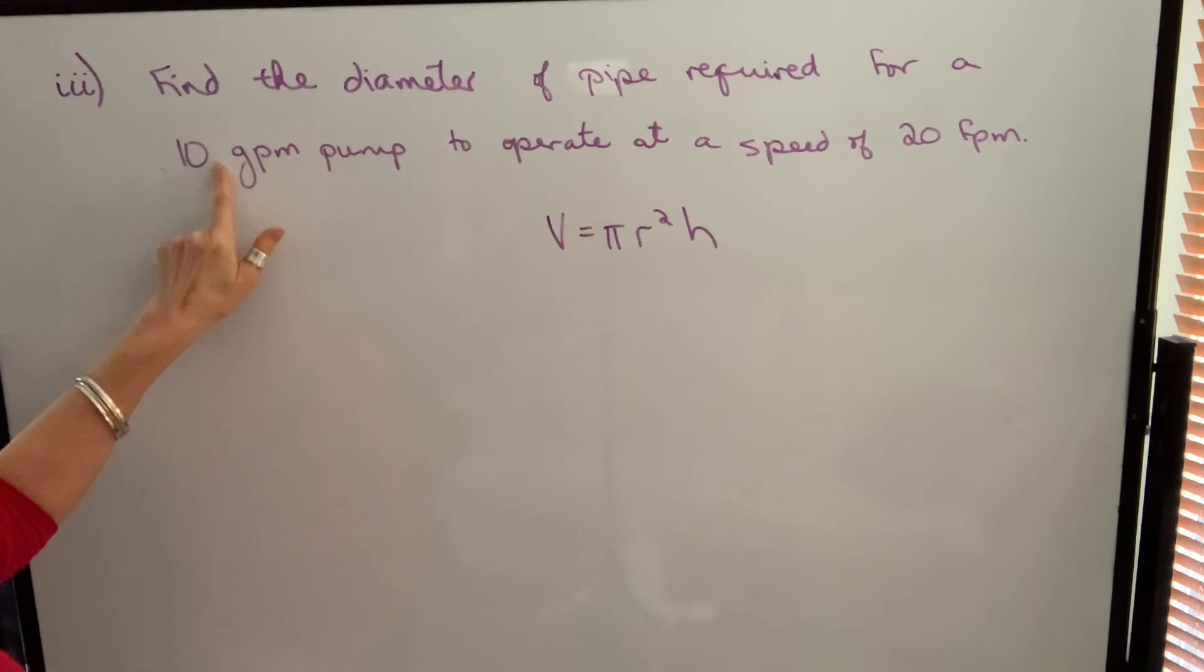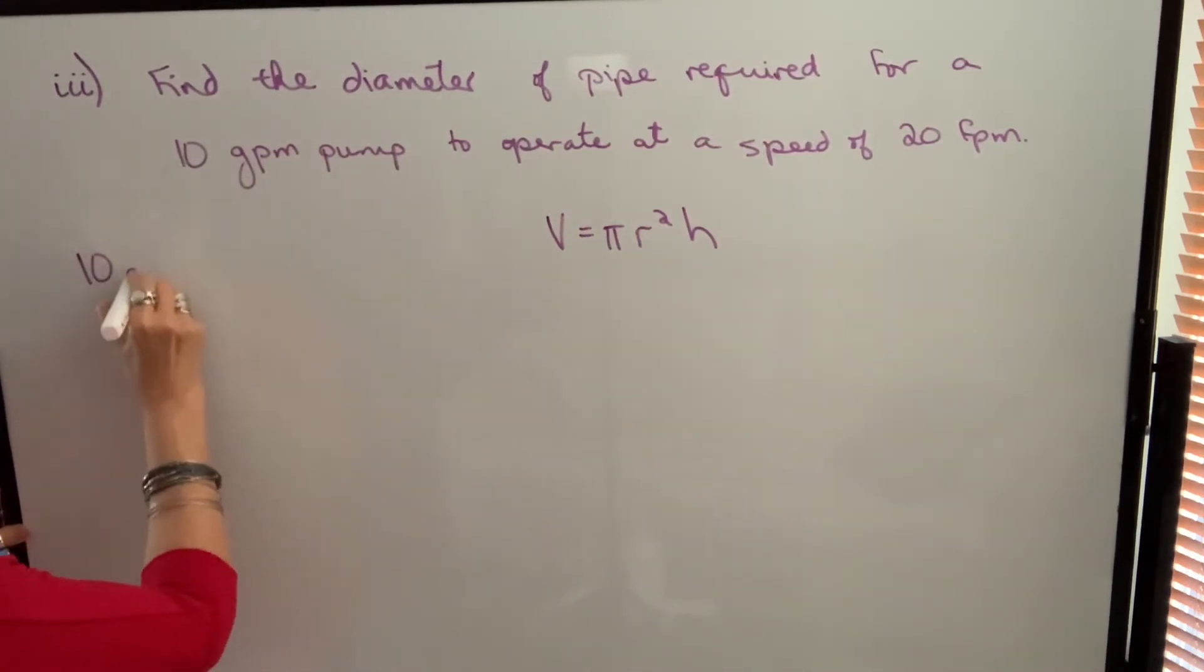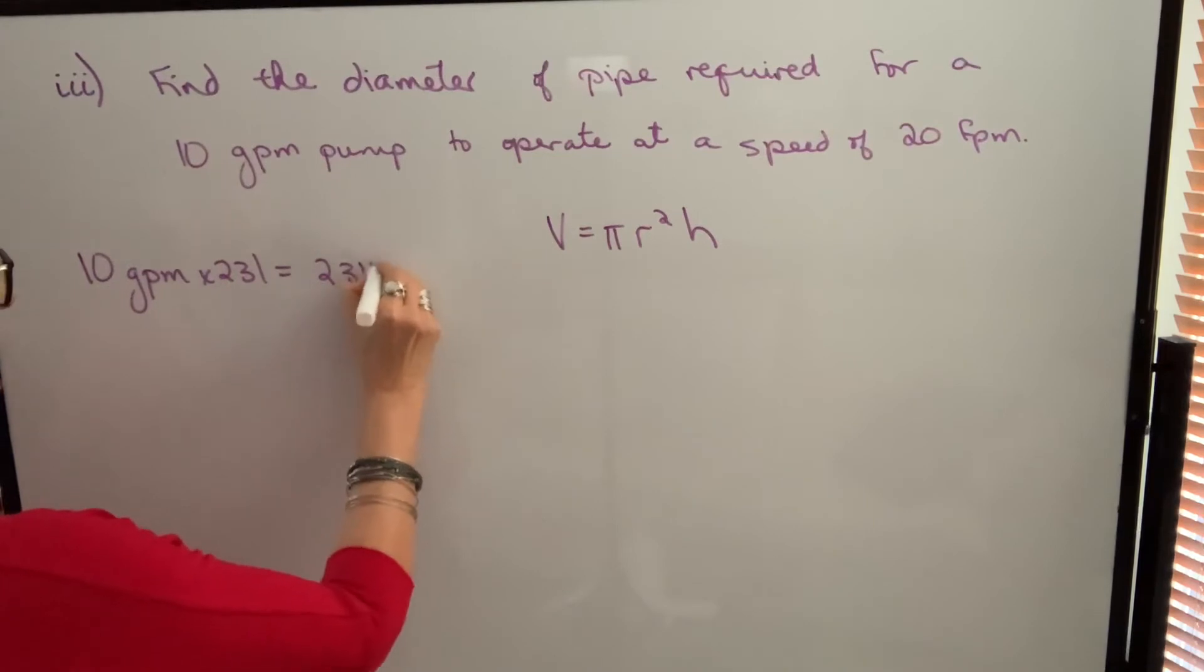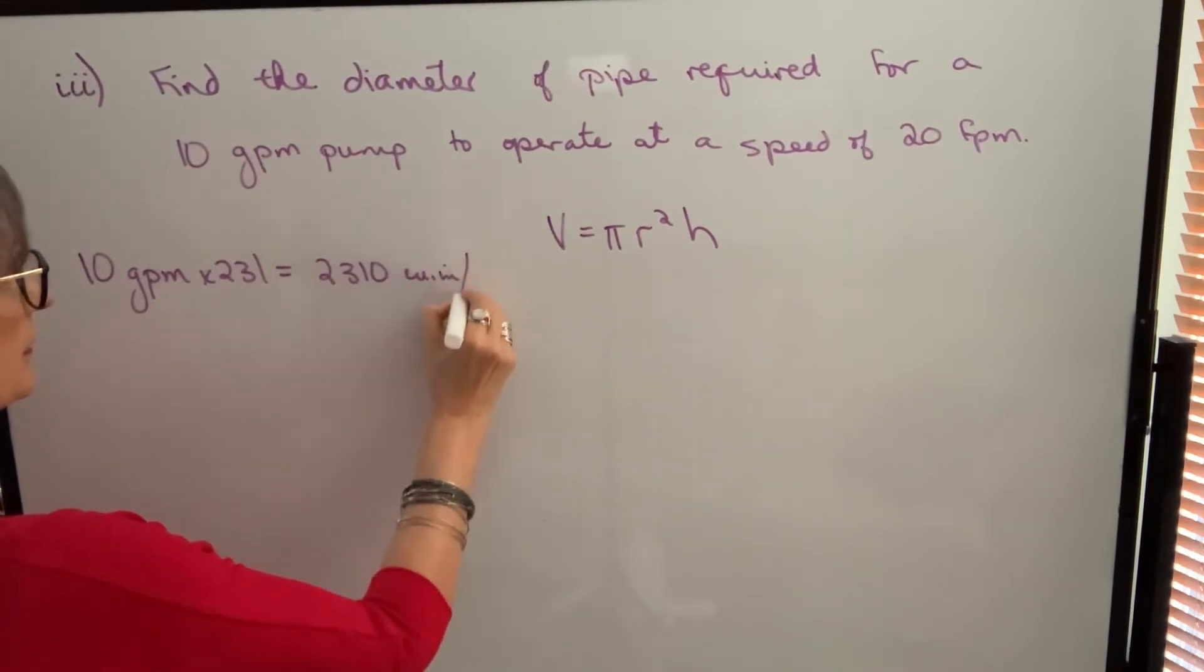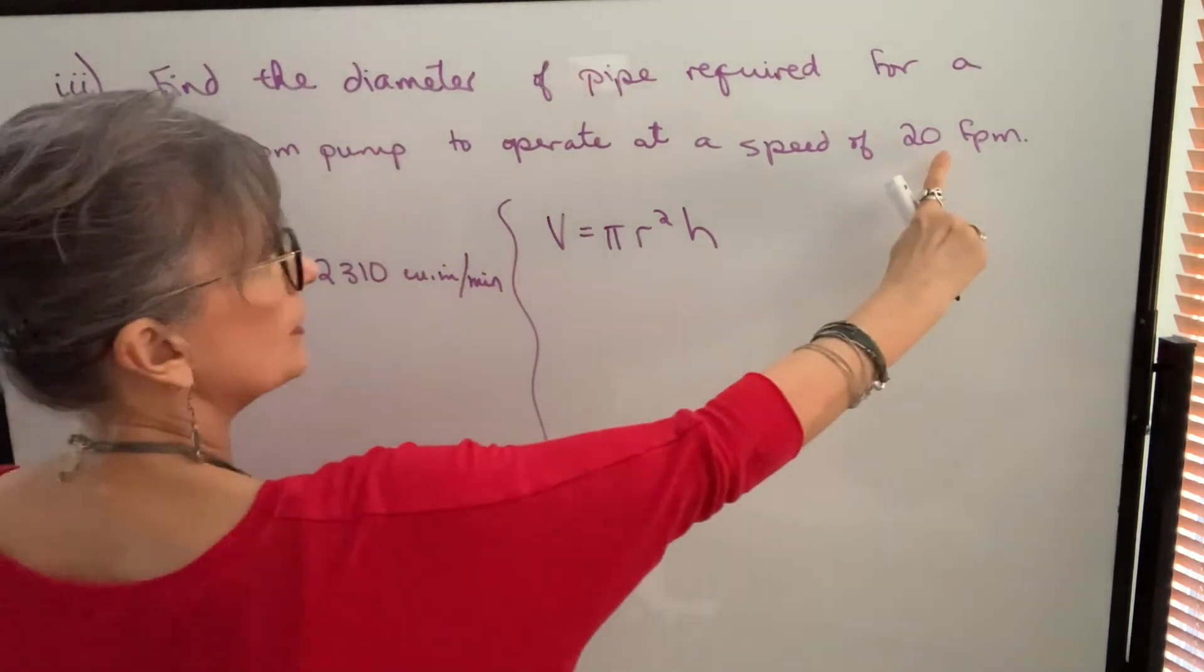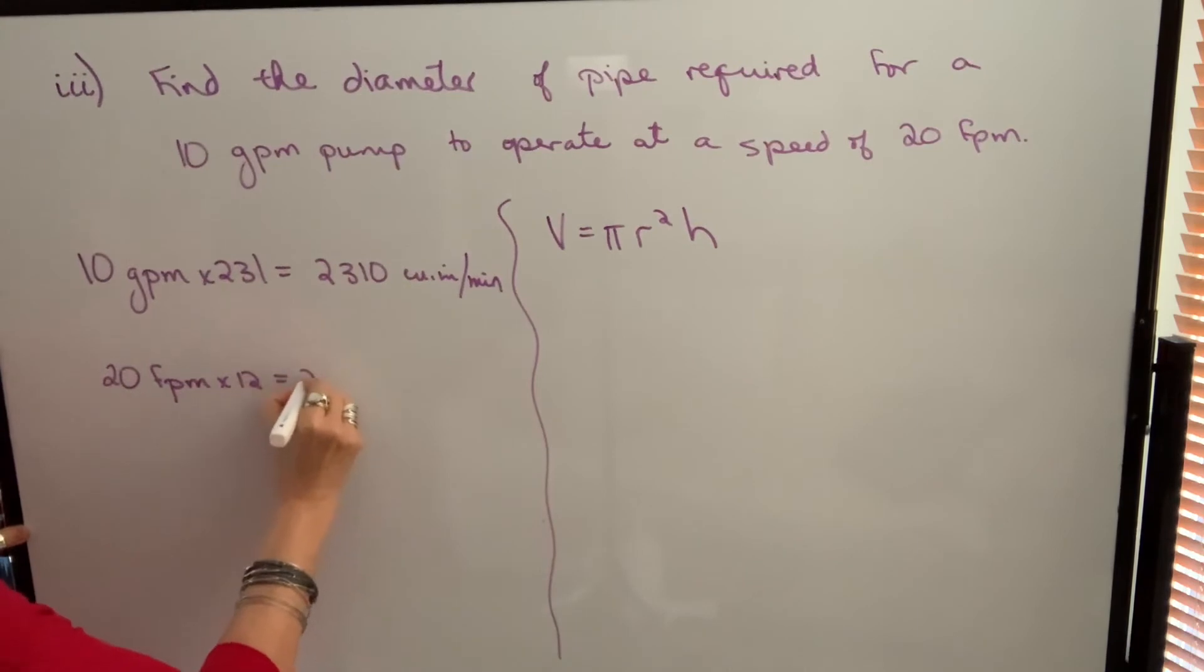So we've got a 10 gallon per minute pump. We're going to change that. Remember, it's all about the units. So 10 gallons per minute, we're going to multiply by 231 and that will give us 2,310 cubic inches per minute. 20 feet per minute would be like the height and we can't work with feet if our other dimensions are in inches. So we're going to multiply by 12 and that will give us 240 inches per minute.